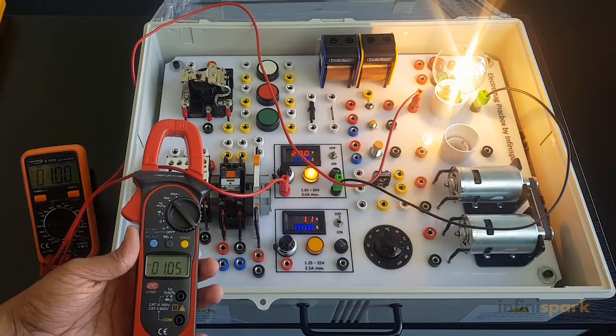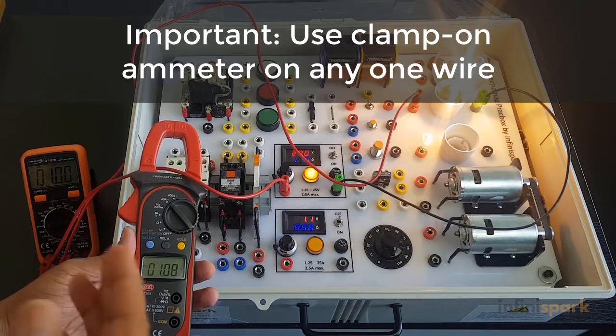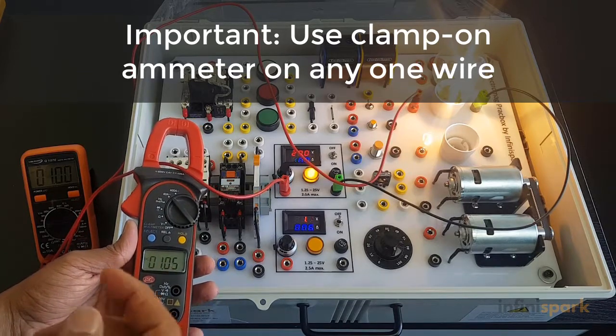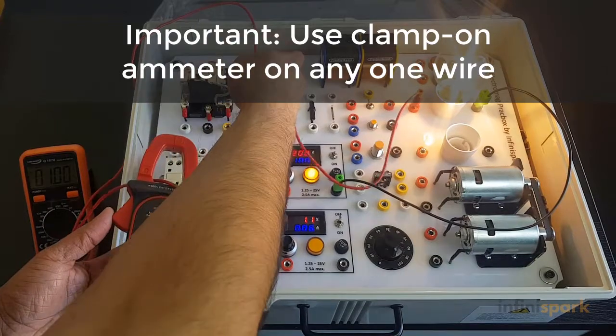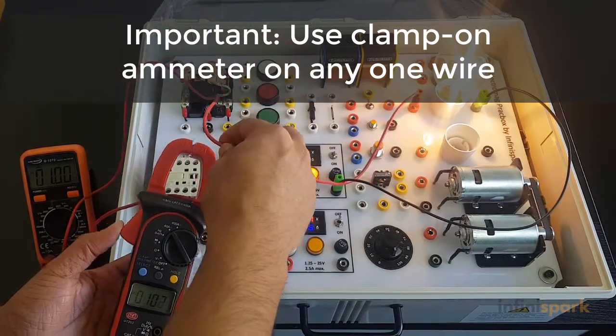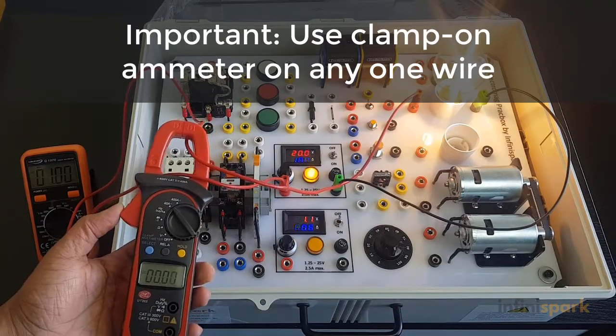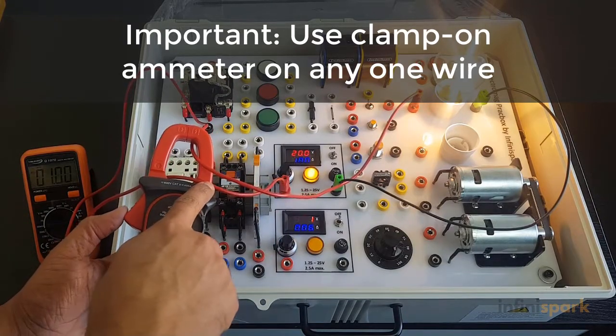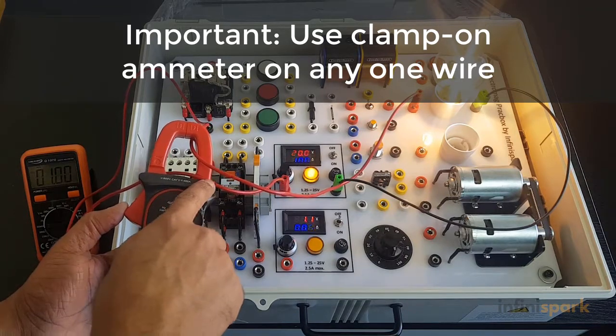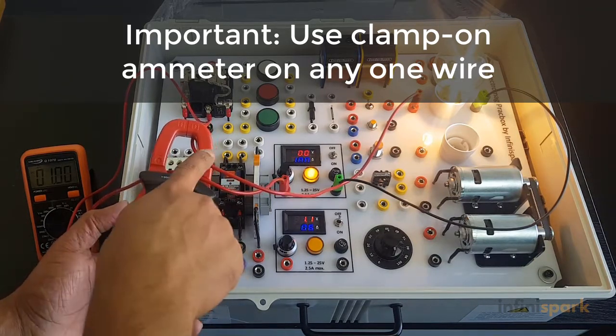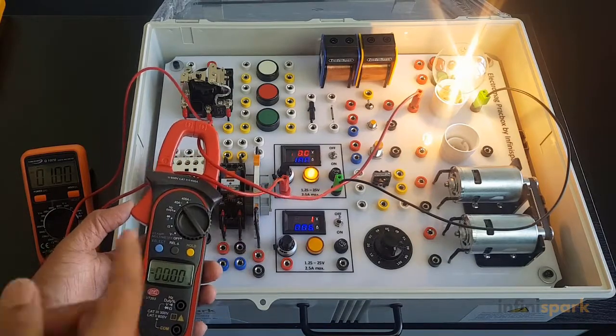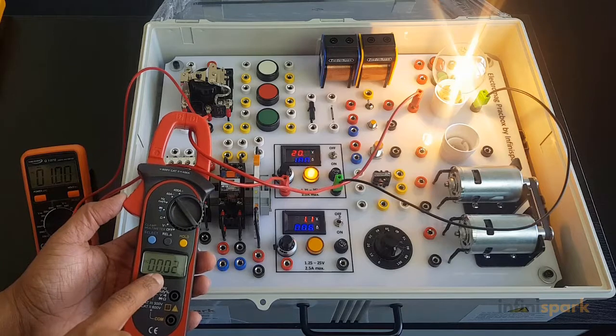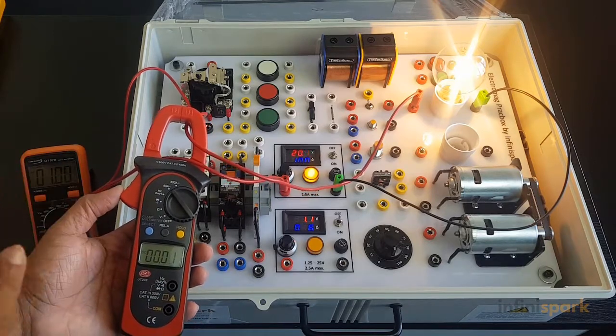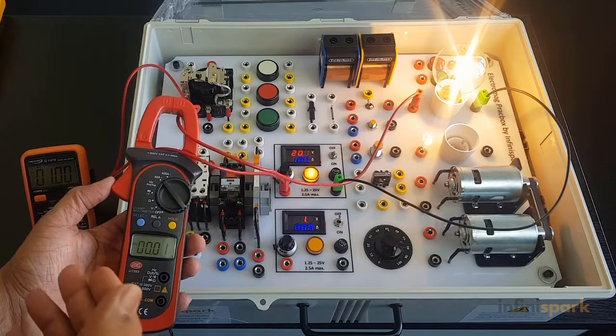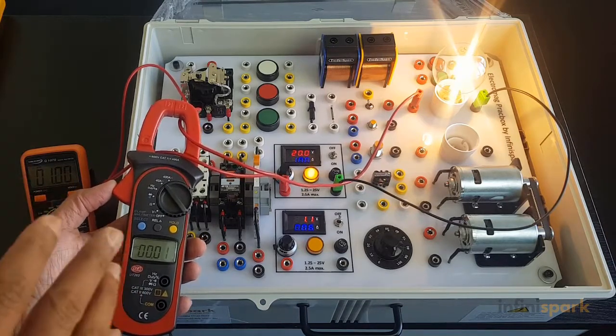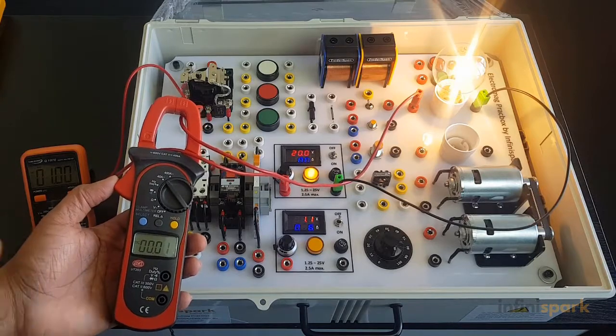Now there is a trick with this clamp-on ammeter. Usually when you install the cables, they're not really single wires, they're multiple cables. There's active and neutral both in there. So if I was to take the current that is going inside and outside at the same time, see what happens. I get no current whatsoever. That's because the magnetic field that this current is generating is canceling out the magnetic field from this one. And since both currents are the same, the net result is zero. So basically a clamp-on ammeter measures the magnetic field of the current and decides how much to display. Now that's for DC. For AC, it uses a mutual inductance, which is another topic.